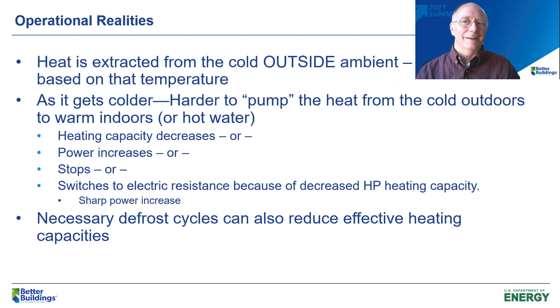So you have to consider not just what the heating capacity is at those temperatures, but how much of the time it will be defrosting, which further reduces that heating capacity. So those are a pretty strong list of problems.